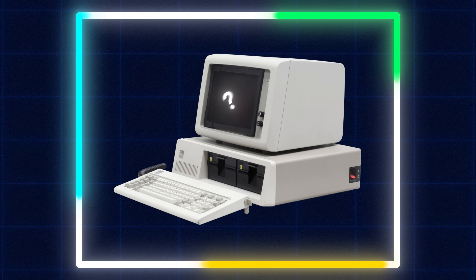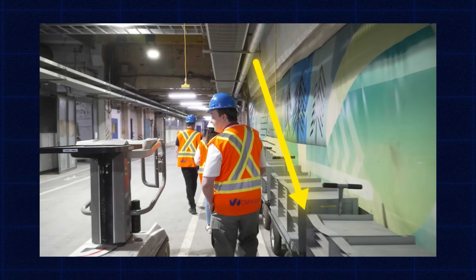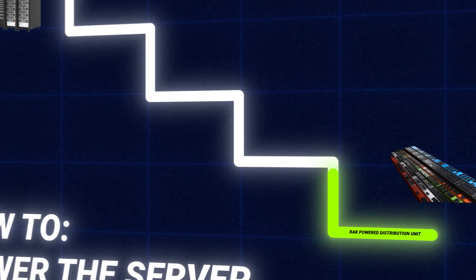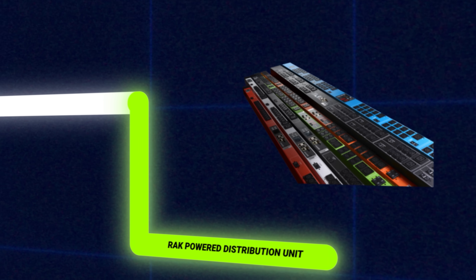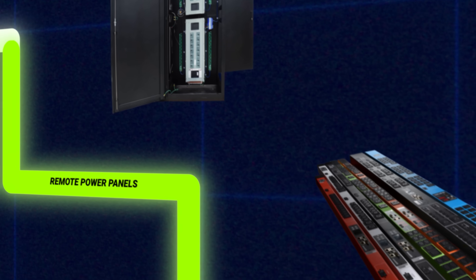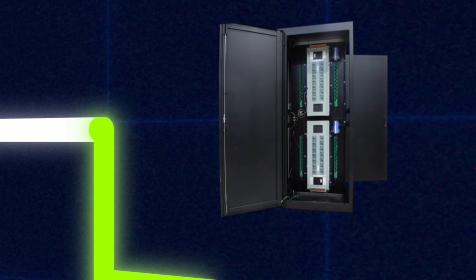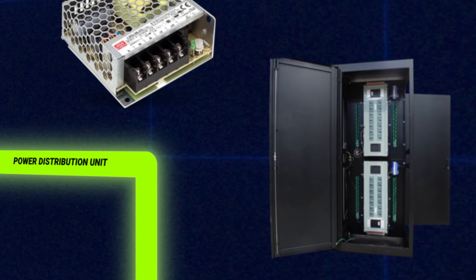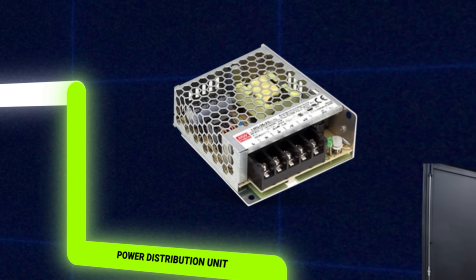Now that the computers are built, how do you set up a server to operate alongside every other server? OVH uses their own custom design racks, just like you see in stock footage, designed to have rows and rows of servers. In reverse order, the server directly gets power from a rack power distribution unit, which is mounted on the entire server rack and distributes power to individual servers. That power comes from a remote power panel, which distributes power from a central source to multiple locations — often there are multiple of these in extremely large rooms.